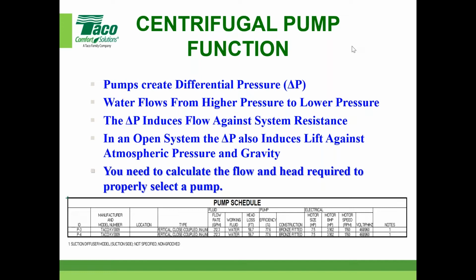But some of our equipment is installed on open systems—probably the most common being a condenser water or cooling tower type system. In that type of system, you also have to worry about lift, which I'll talk about more on another screen. In a closed loop system, you don't have to worry about lift for your system resistance, only for the pressures.